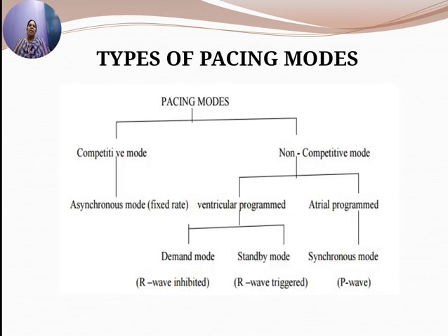Then coming to the types of pacing modes. Pacing modes are classified into two types, competitive pacing mode and non-competitive pacing mode, as I told you earlier. Competitive is asynchronous and non-competitive is synchronous mode. Competitive pacing mode, or asynchronous mode, is a fixed rate mode.